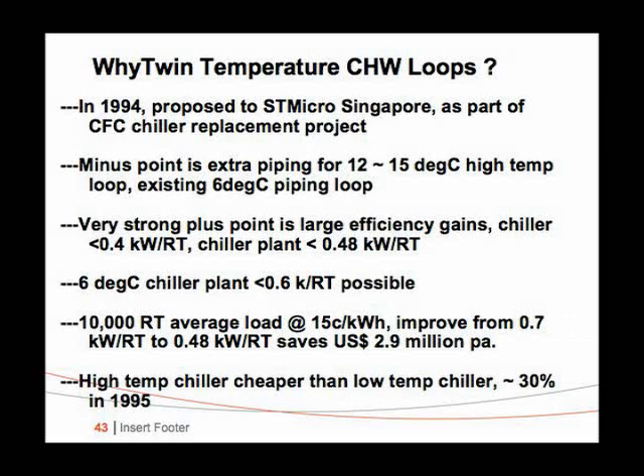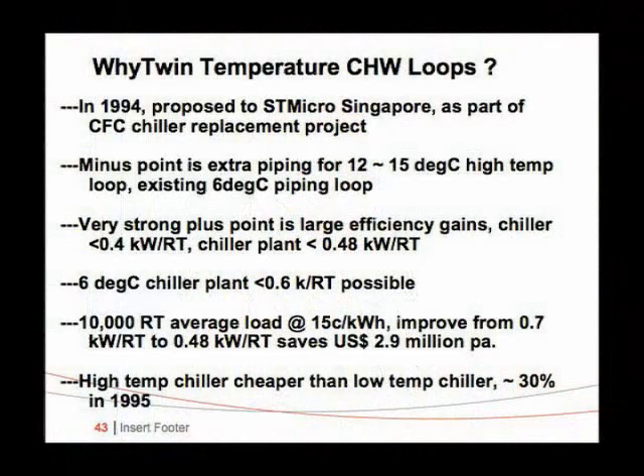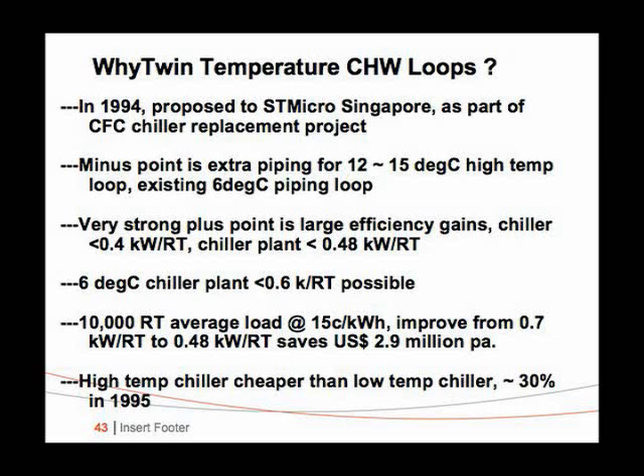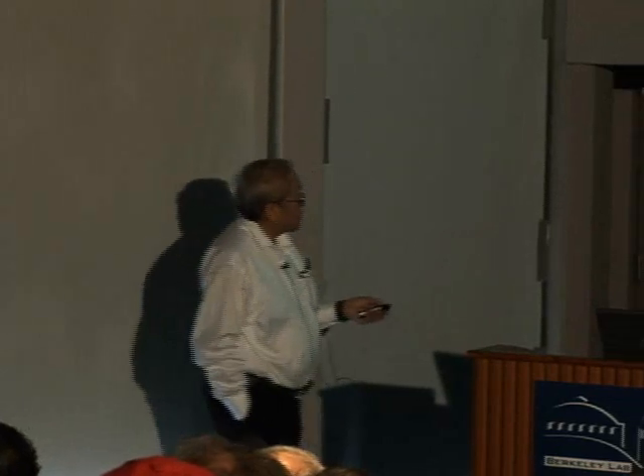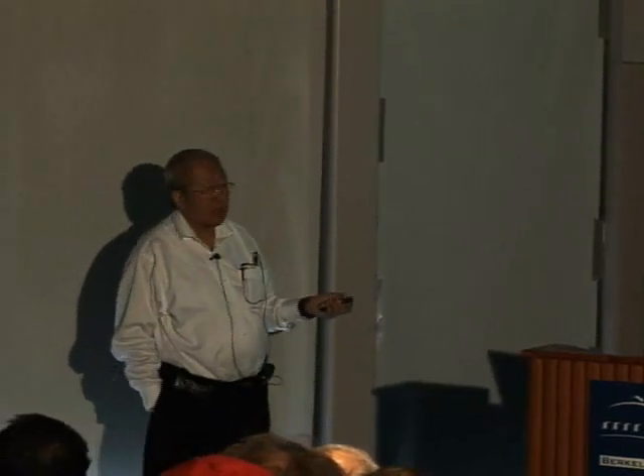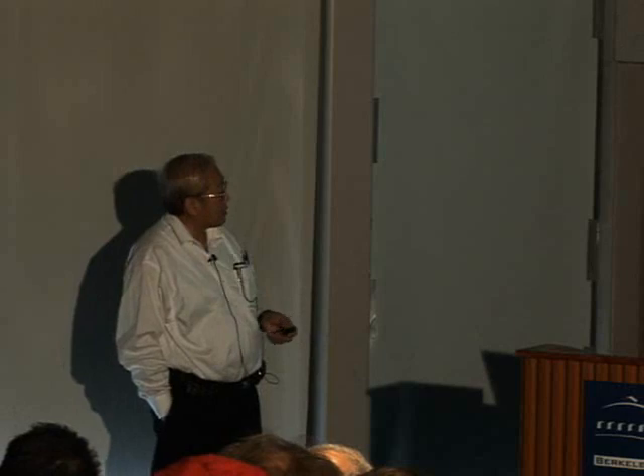So why do we use twin temperature loops? Quite straightforward, thermodynamic reasons. CFC project, we need extra piping because now we have two sets of temperatures to handle. But the very large gain is you can get a chiller at below 0.4 kilowatt per ton, in case any of you are in the business, and you can get the plant to 0.48, which I believe was a world record at the time it was installed in 94 or 95. And of course, now you can get chiller plant. TRANE is routinely offering better than 0.6 in tropical conditions.